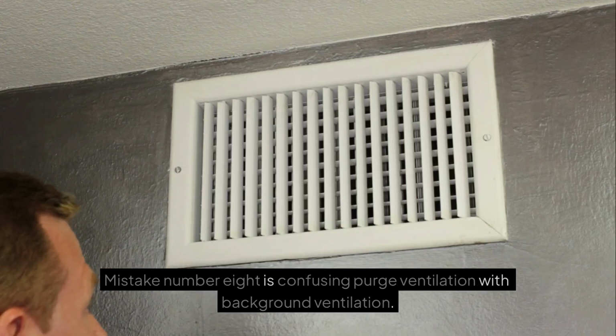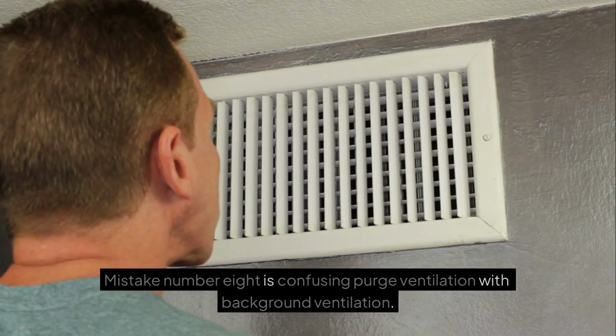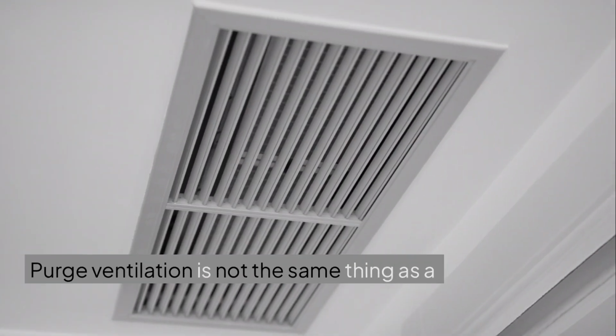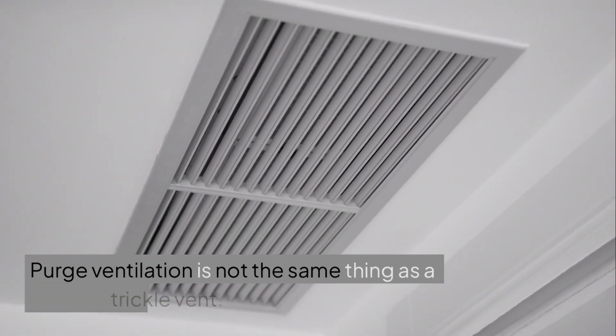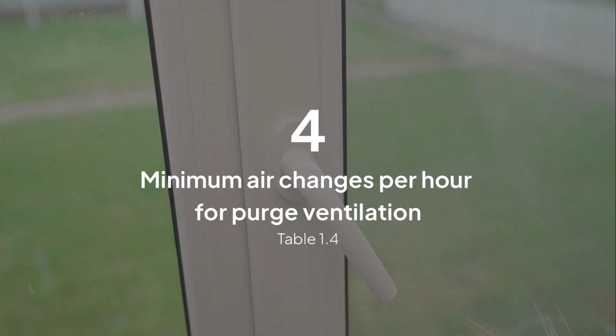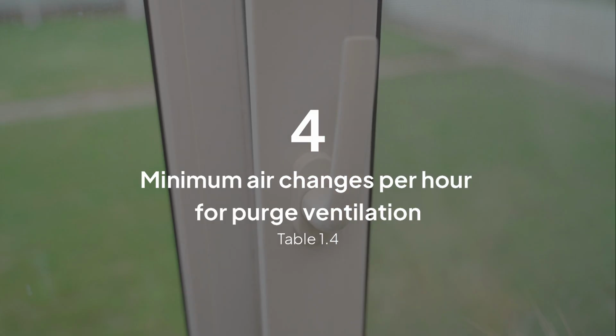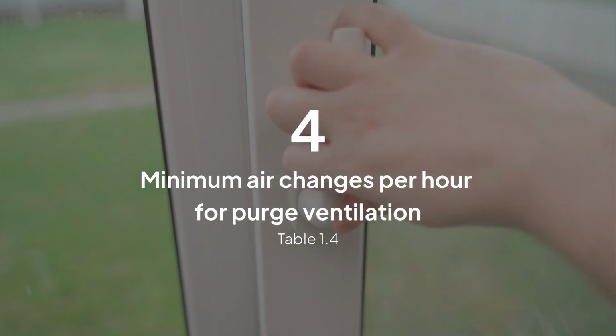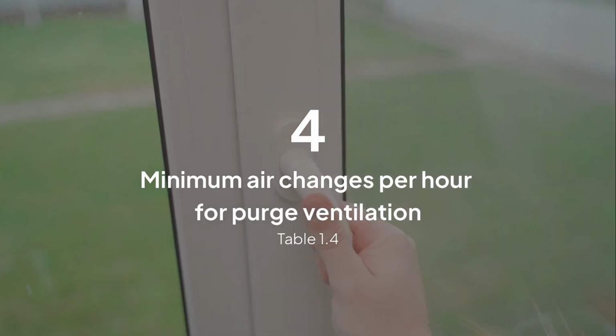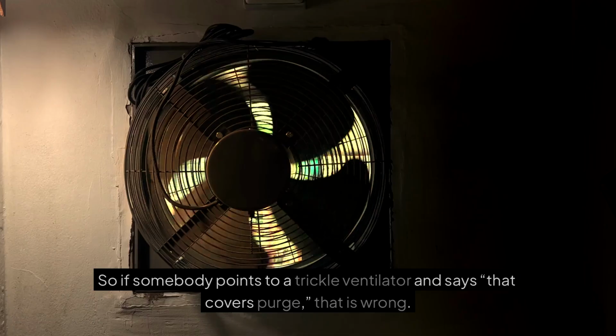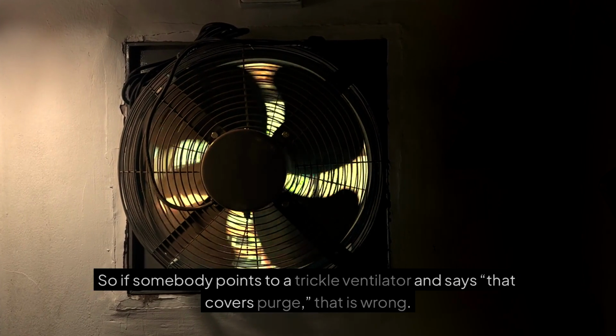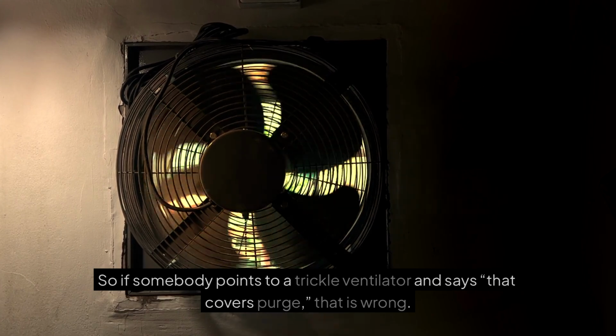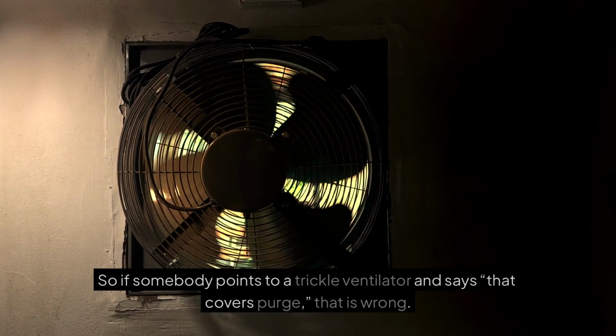Mistake number 8 is confusing purge ventilation with background ventilation. Purge ventilation is not the same thing as a trickle vent. The document says each habitable room should have a system for purge ventilation capable of at least 4 air changes per hour directly to outside, and if openings are used, Table 1.4 gives the minimum area depending on the window type and opening angle. So if somebody points to a trickle ventilator and says that covers purge, that is wrong.